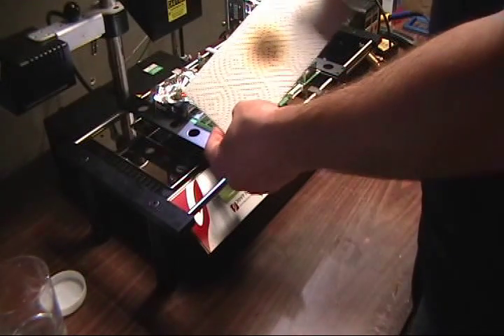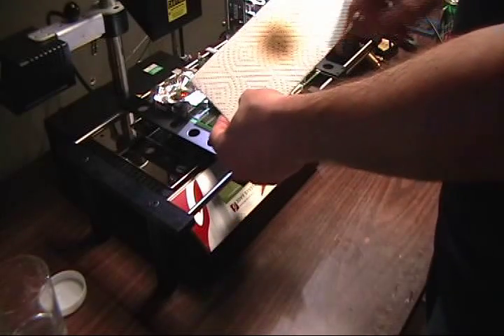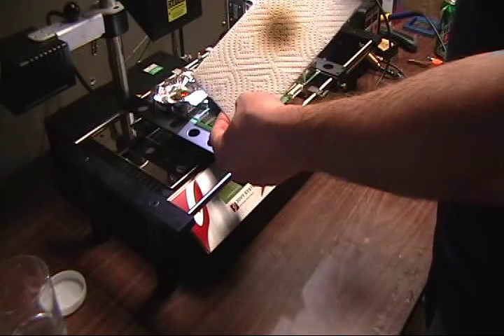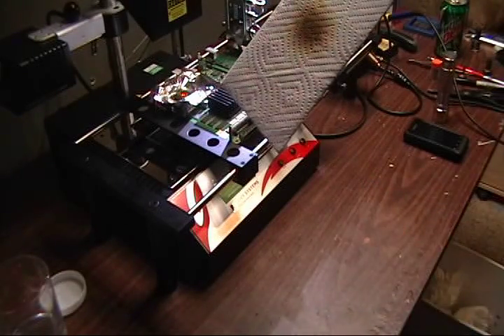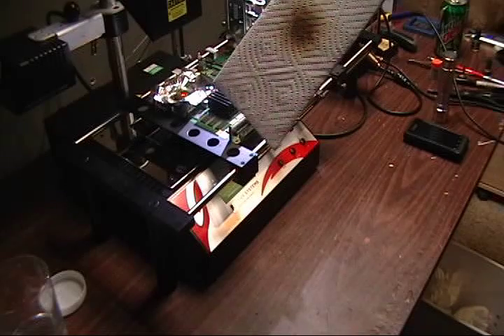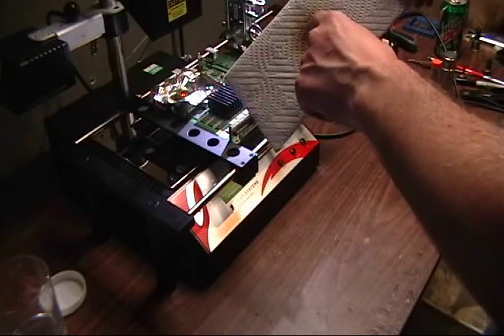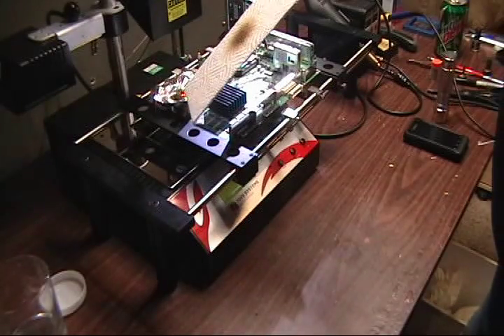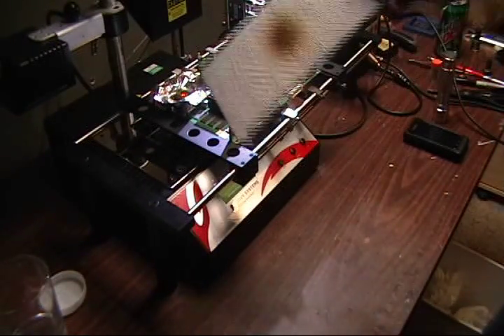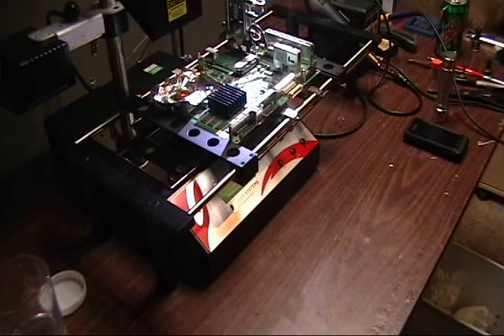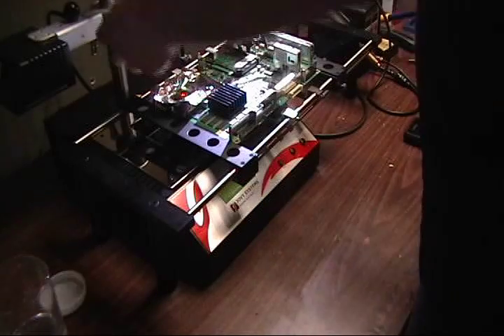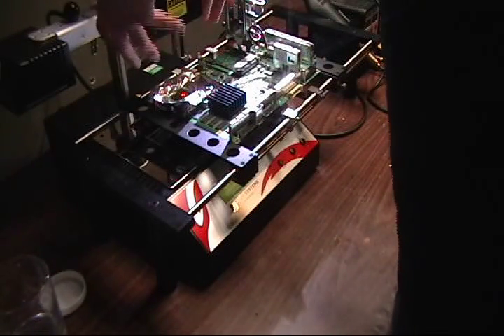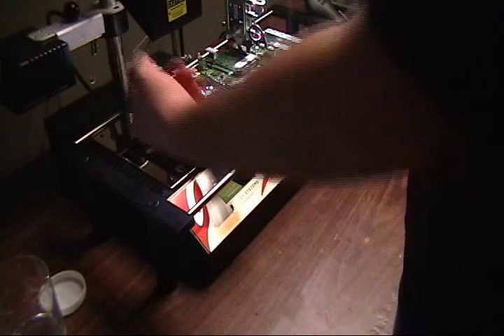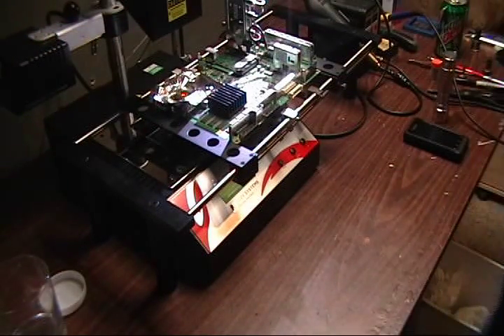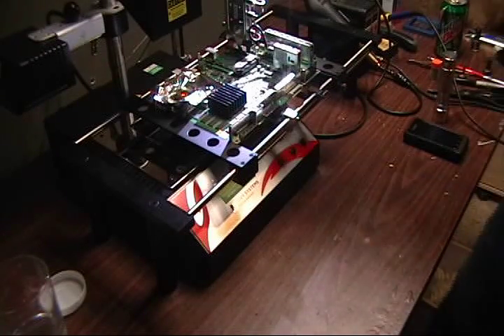And make a mark where your laser was, and maybe make a small circle. I don't know if you can see that. But you have to calibrate basically where the heat from the upper heater is, because the laser might be there, but it's actually heating behind it, and you want the center of your heat where the laser's at. You do that by prying this thing up and down. Even when I got this, I had to push the upper heater down, because it was kind of bent up. Okay, I'll shut up now.